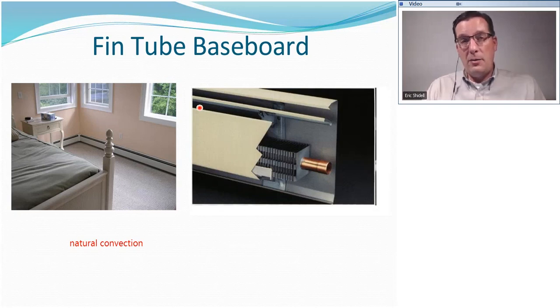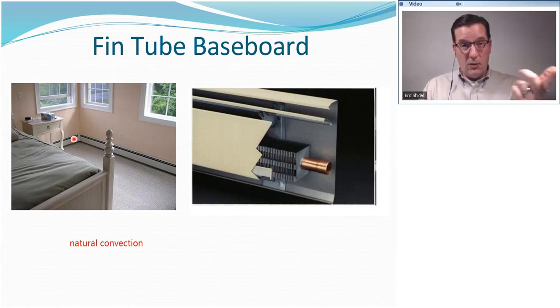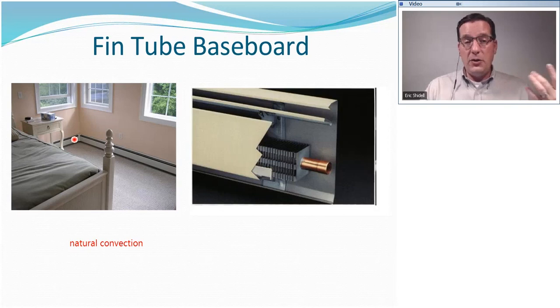Another problem that these can experience is dust and dirt, cat hair, dog hair, accumulating on the underside of the fin tube. It's always a good idea, especially if we're experiencing a challenge heating one room, to stick your fingers in here and feel, is it getting warm? You may need to feel over here in the corner because there will be a bare pipe over there, so you can actually feel the pipe. If you feel the aluminum, it's just usually going to feel, you know, room temperature. Feel the actual copper pipe and see whether there's warm water circulating through it. If you do have warm water circulating through and the problem is that it's not heating the room, we've got to see what's preventing the airflow.